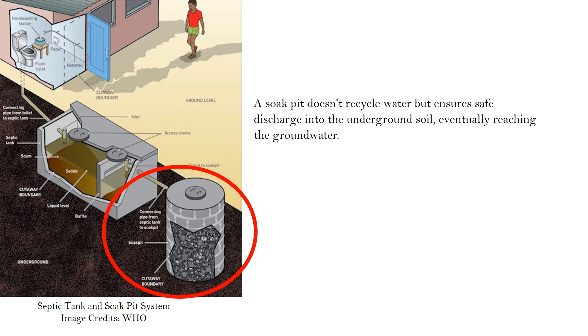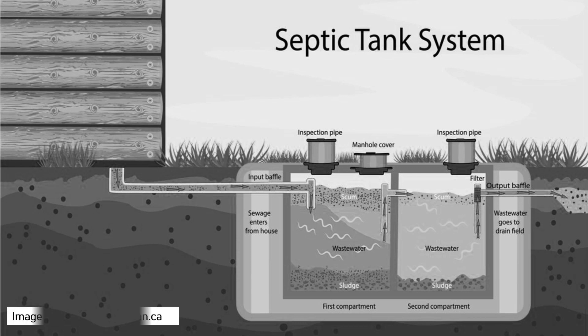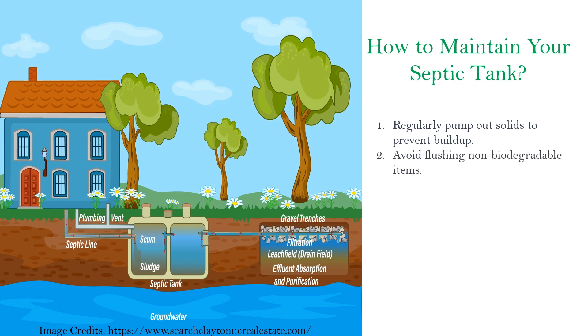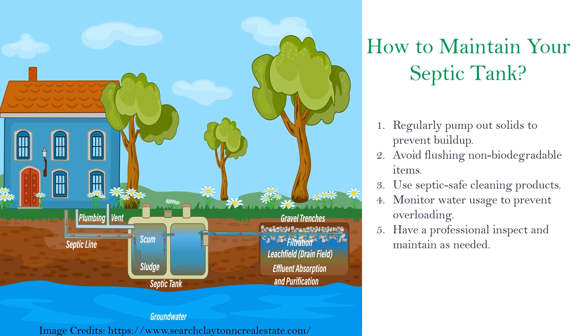Proper design, construction, and maintenance are crucial for the septic tank system to work effectively. Remember, the outlet must be lower than the inlet to prevent overflow. To maintain your septic tank: regularly pump out solids to prevent buildup, avoid flushing non-biodegradable items, use septic-safe cleaning products, monitor water usage to prevent overloading, and have a professional inspect and maintain the system as needed.